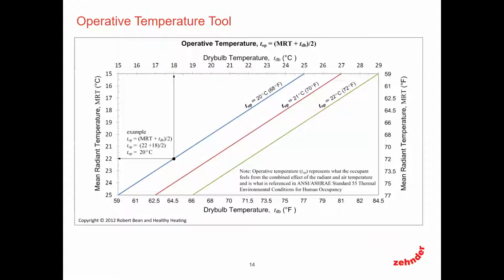There are a number of tools out on the market that you can utilize because I'm not going to lie, it's quite a long calculation to come up with your operative temperature because it's a weighted average of all your controlled surface temperatures versus your uncontrolled surface temperatures. And generally, we all don't have time to make those calculations per space.